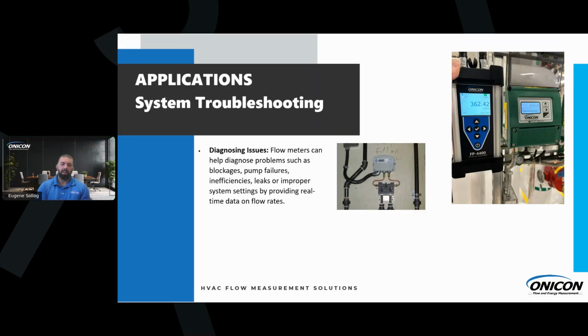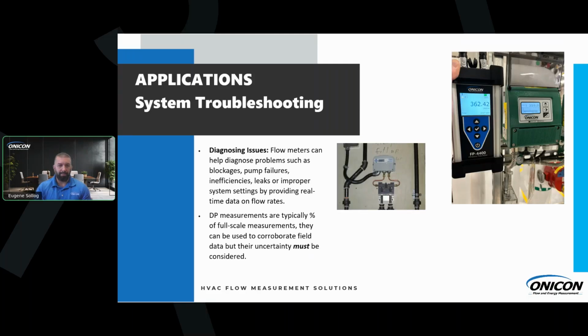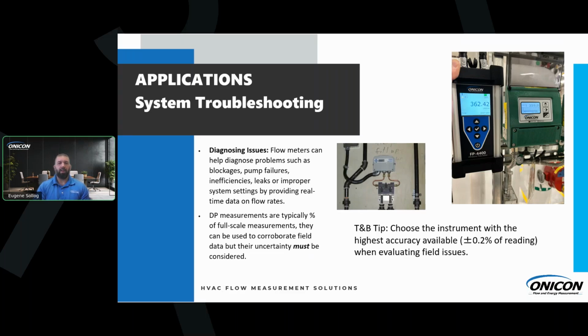inline mag meter. As a rule of thumb, taking a DP is going to be typically a percentage of full-scale device. We didn't really dive deep into the accuracy because these inline mag meters are a percentage of reading device, not a percentage of full-scale device. So when looking at these types of installations where you have a balancer coming out, keep that in mind: they're not always as accurate, especially when comparing to a plus or minus 0.2% of reading flow meter.